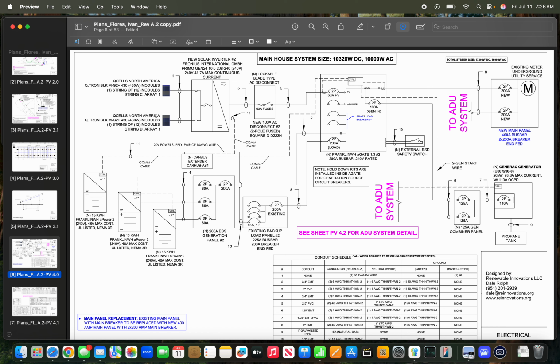And then you can see we have 2 strings of 12 going to the Fronius Gen 24 inverter. And this was something that is important to note. The Gen 24 inverter only has 2 MPPT inputs, and they also do not support parallel connections. So the original design had 3 strings. That wasn't going to work. I had to get them to change that. And that's reasonable because most string inverters today have 3 MPPT inputs or 4. So why Fronius has decided to do 2, I don't know. But honestly, I don't think it's too bad because it works out pretty well for this ground mount system and keeps it really simple.